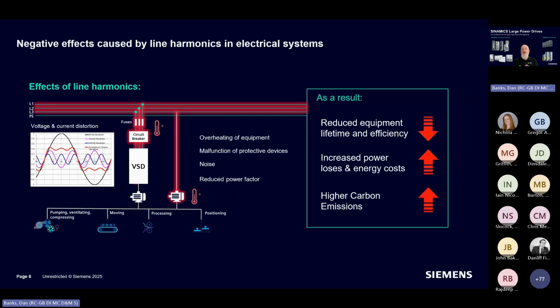So I mentioned non-linear loads earlier, and this is why this is becoming a much bigger issue in this day and age. Non-linear loads is really anything that doesn't draw power smoothly. So a VSD is a non-linear load in the sense that a standard 6-pulse drive pulls chunks of current as and when the diodes open. But almost everything is a non-linear load.